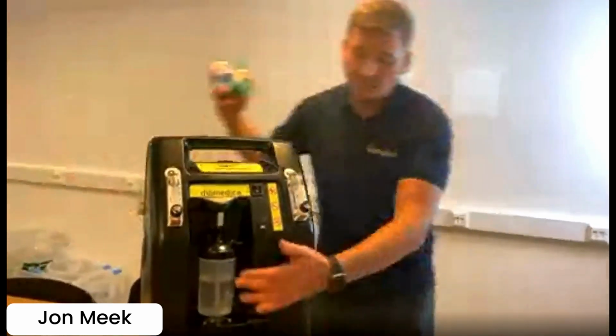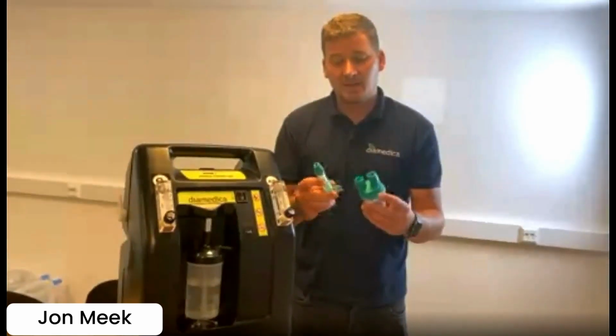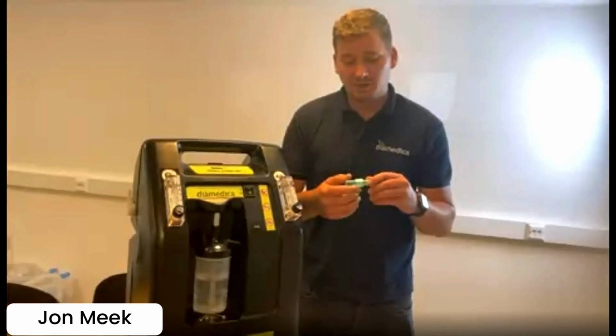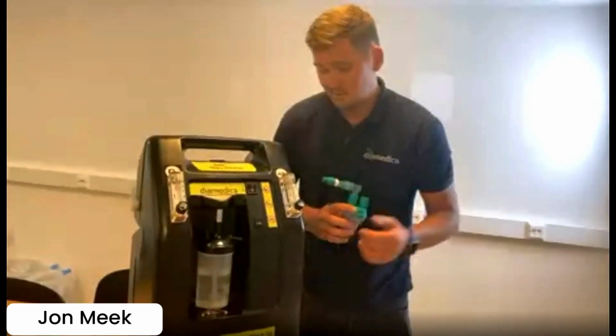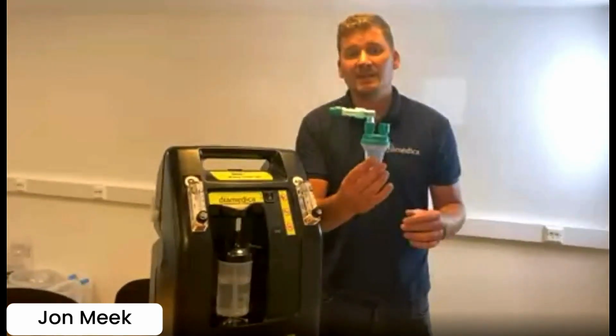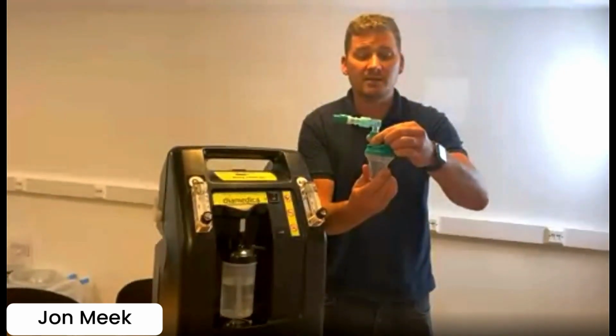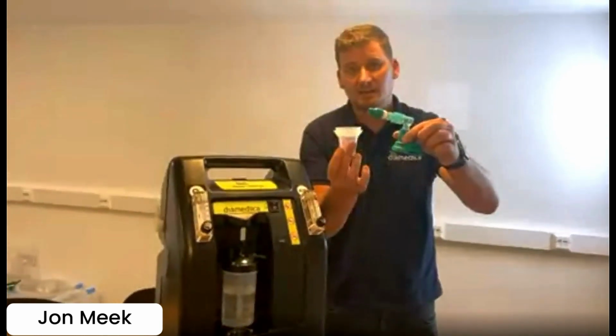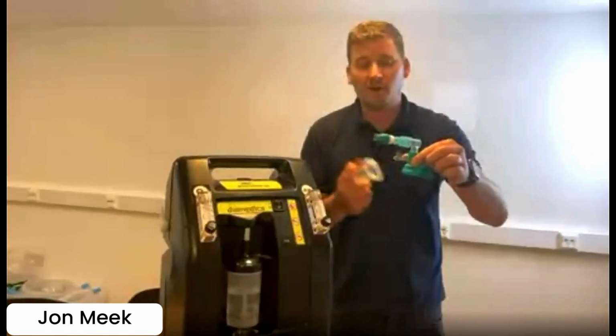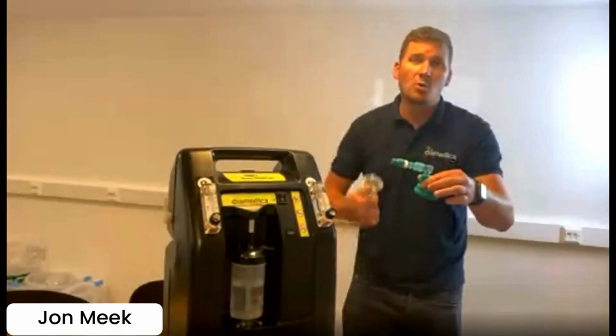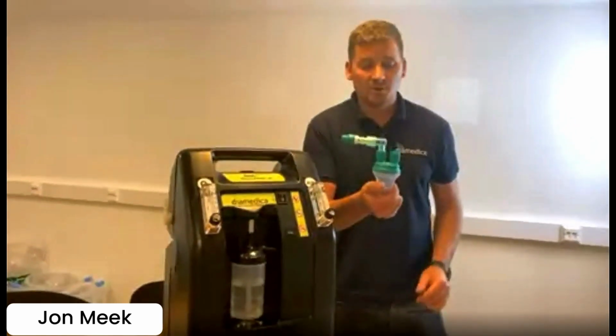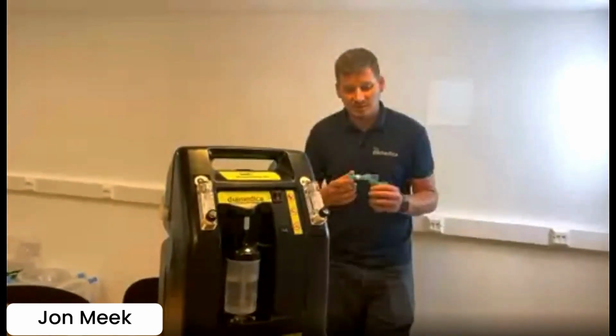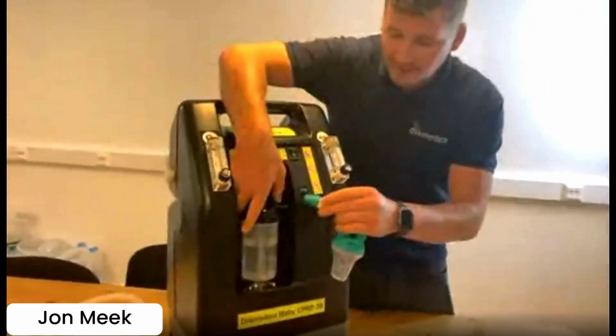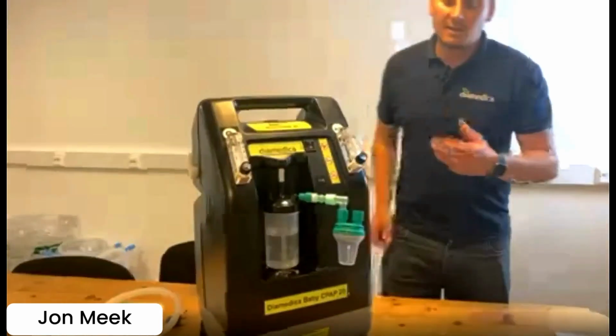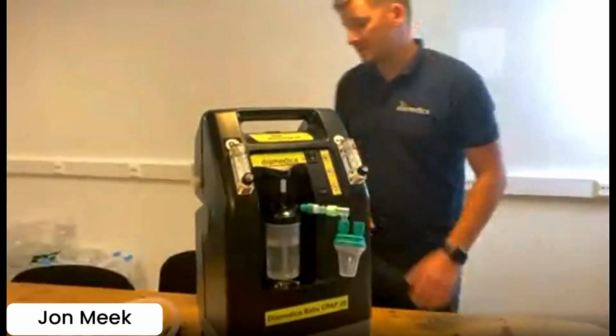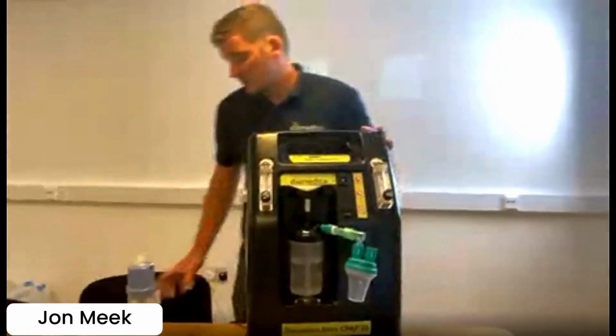So coming out of the humidifier bottle, we do fit a water trap, to ensure that any moisture that does flow over from the humidifier bottle is caught in this water trap. This is a self-sealing water trap. So if it's in circuit and you disconnect to empty the water, it bypasses the drain, and it still passes the oxygen and air mixture through. So you don't have to switch it off or on when emptying or filling, which is really important. You don't want to keep stopping and starting the machine when it's on CPAP, providing it to a patient. This just connects on, hold the bottle, fits onto the side, as so. And it works both ways. It doesn't have to be a direct way. That's the humidifier bottle on the side.